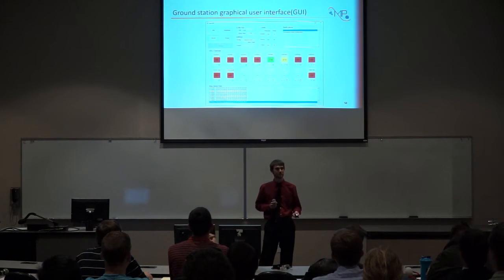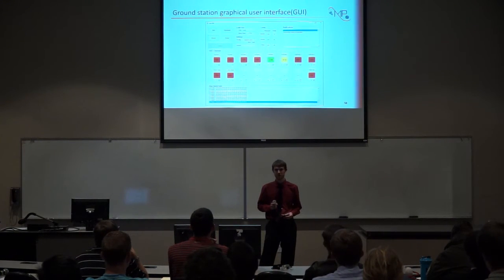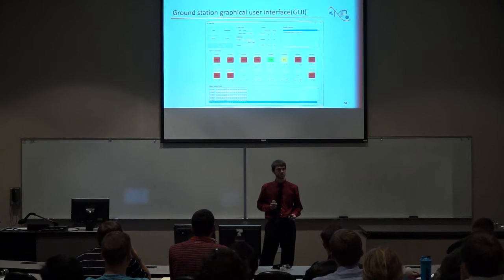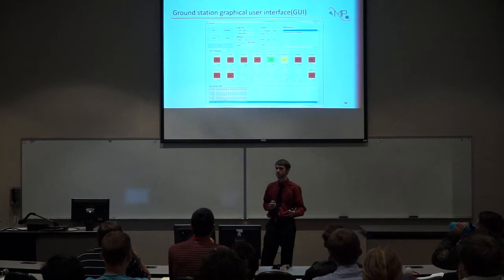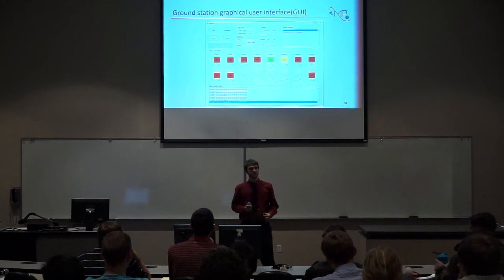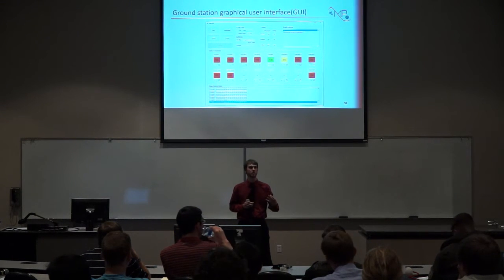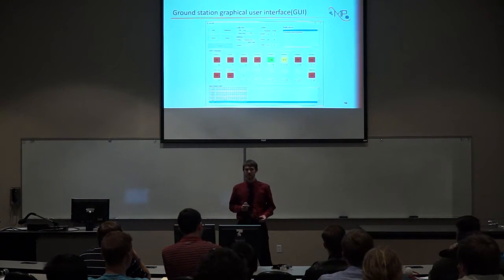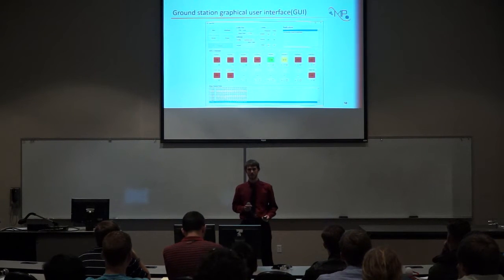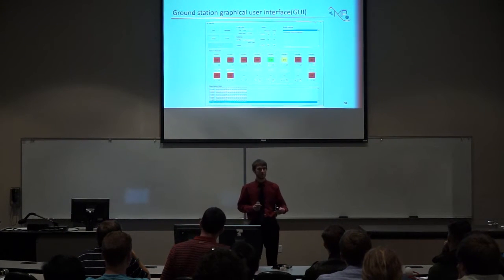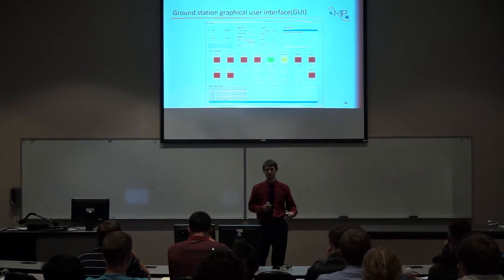As I said before, the analog to digital converter has 16 channels, so the GUI supports all 16 channels. As you're setting up the GUI, you're able to set every single channel to a pressure, a temperature, or a load cell, and then you're also able to calibrate those channels so that they have nominal operating points. So you're able to set sensor data coming in to be at a nominal point, at a warning point, or at a critical point, which would most likely need operator input.